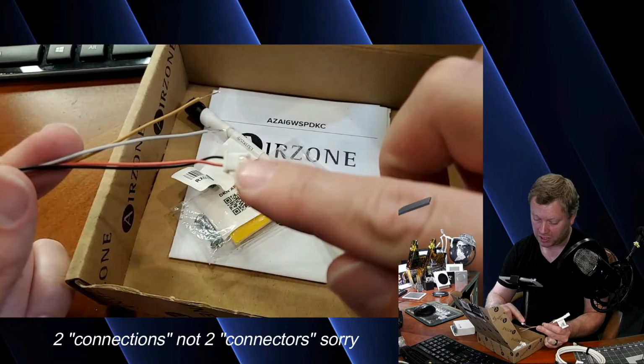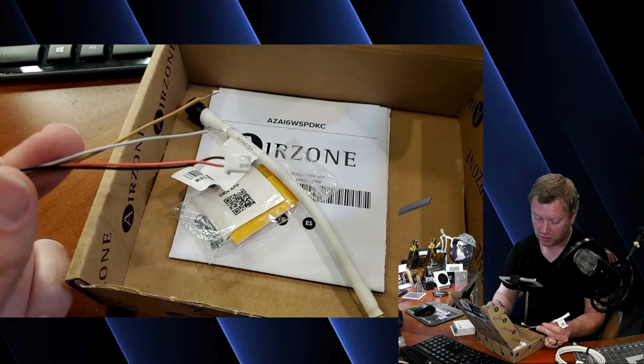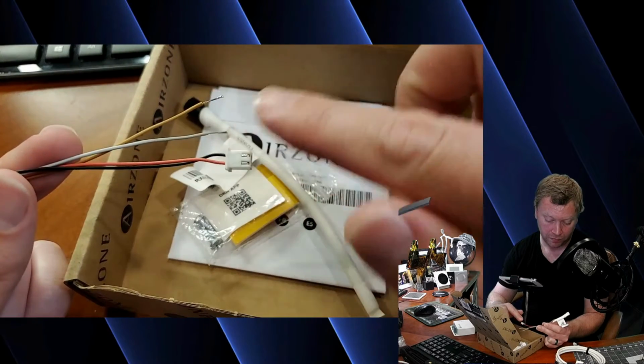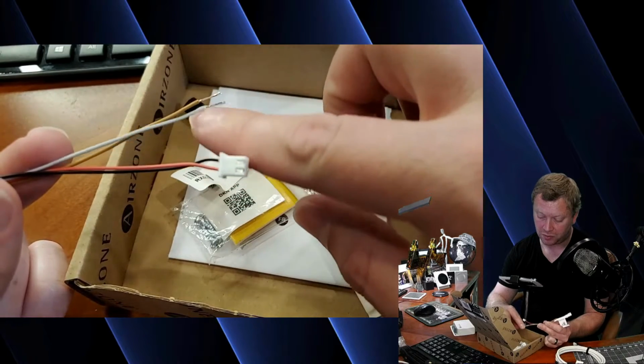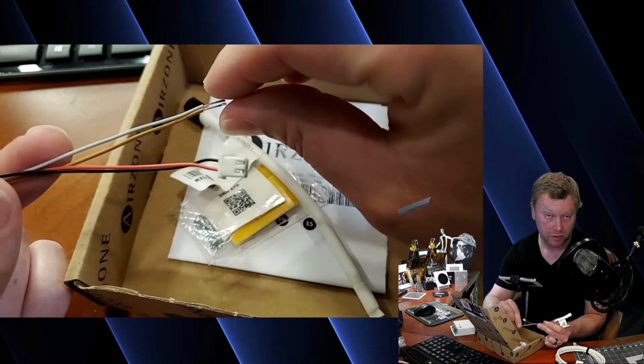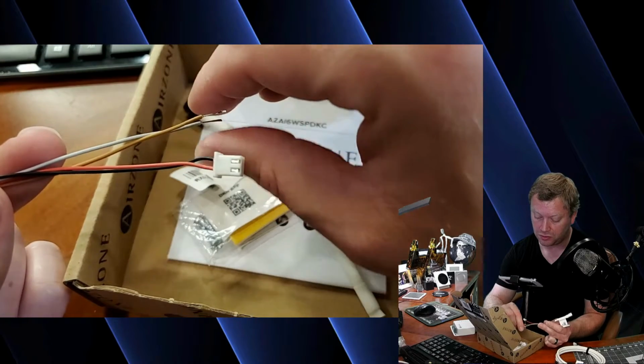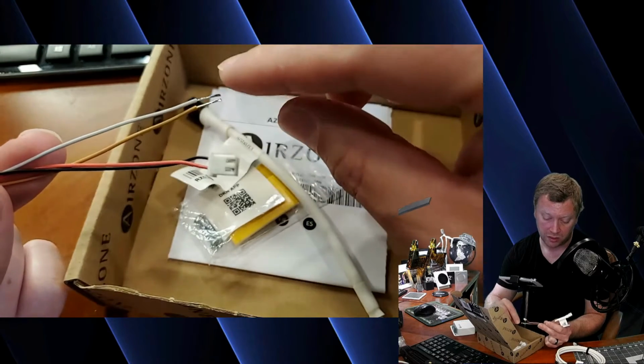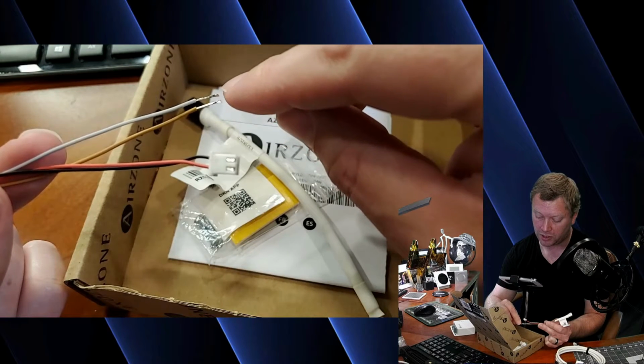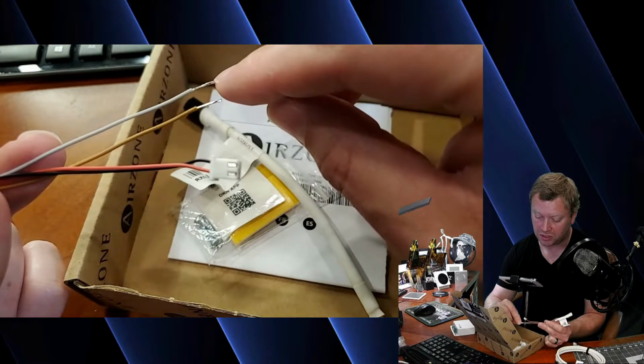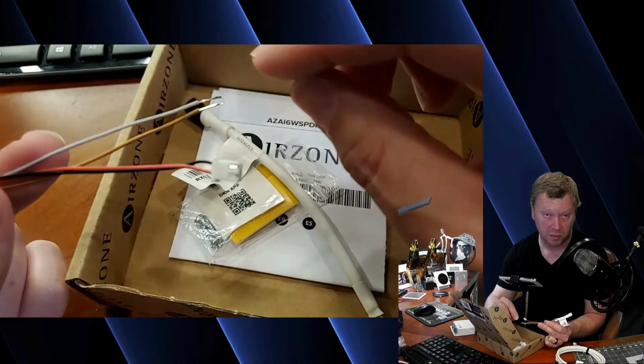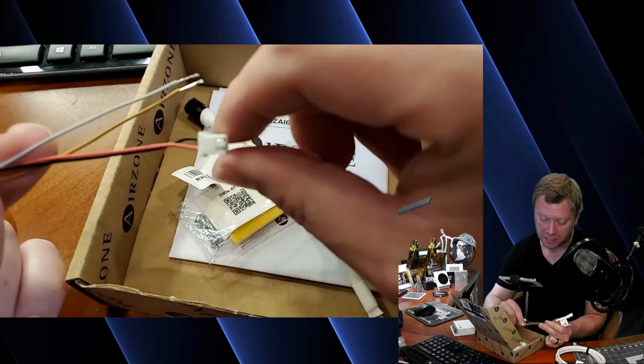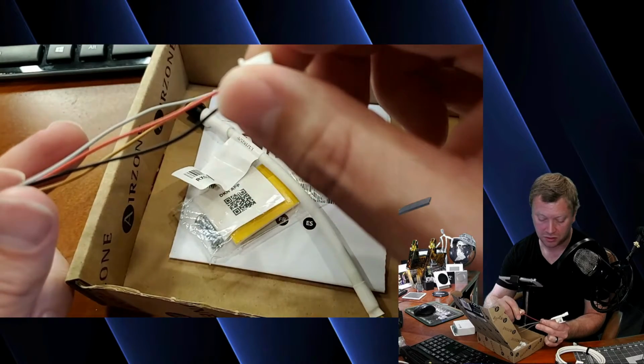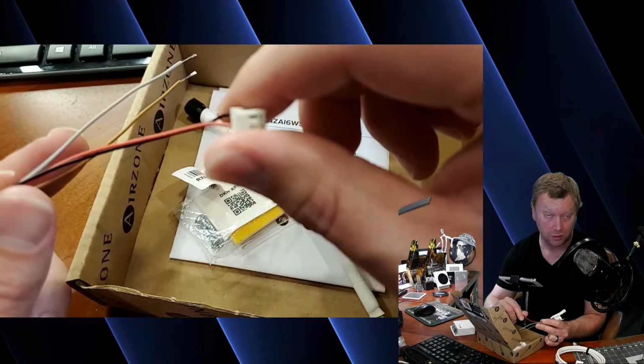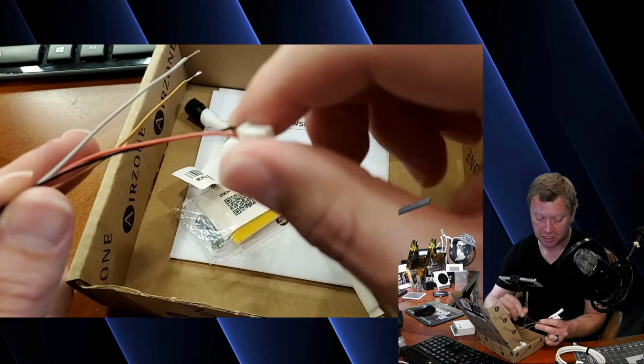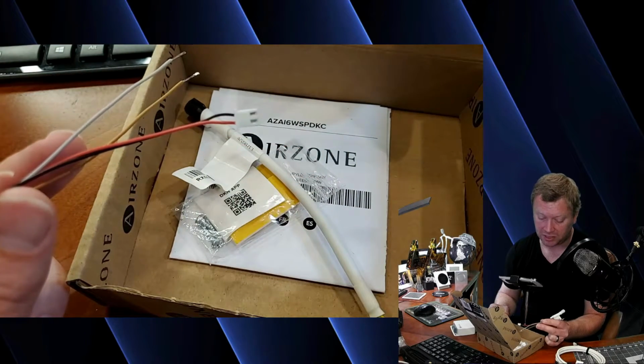So this white connector here is going to be where you get power. These two wires are going to be your P1, P2 wires. Now, if you guys recall from past videos, P1, P2, they are non-polar. So either one of these two wires, gray or brown, can be plugged into P1, and either one of these wires can be plugged into P2. Does not matter. It's non-polar. And then this connector here is going to plug into a particular connector on the indoor unit, which I'll talk about here shortly. And again, this is going to power the DKN Plus adapter.